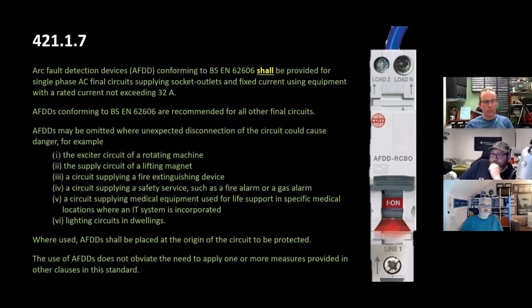So if you had a radial circuit with washing machines, fine, but remember, if that's an inverter drive washing machine and that's all that's working on that circuit, say it's 500 watts, the AFDD will not see the arc. This is only the problem if it's a minimum load issue, you need a minimum load, and AFDDs are brilliant, but you need a minimum load on that arc. If you don't have that minimum load on that arc, they do nothing - they're just an RCBO, and a really expensive one at that.